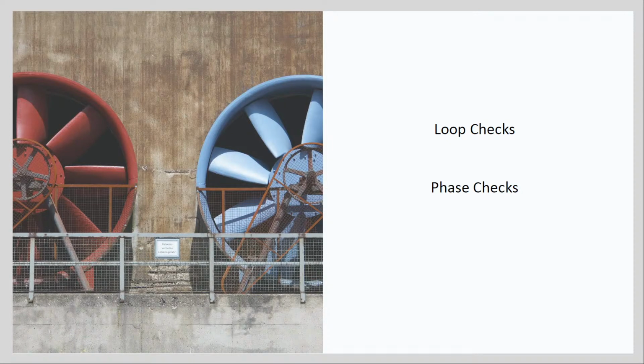So this includes verification that the polarity is correct for each PT and CT. This is something to watch for because I've seen situations where you have a backwards wired CT. As soon as you go to do your first energization, the unit's going to trip off instantaneously because it's going to see current that's going in the wrong direction. So you definitely want to make sure that the polarity of your PTs and CTs are correct. But you also want to watch that you're not getting two negatives, a backward CT plus a programming error in the PLC, which is displaying correctly on the HMI, but in fact, you're getting a false reading. I've seen instances like that occur as well.